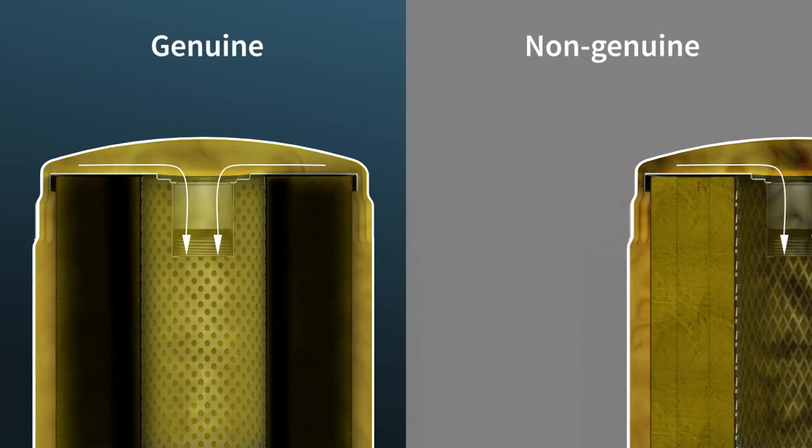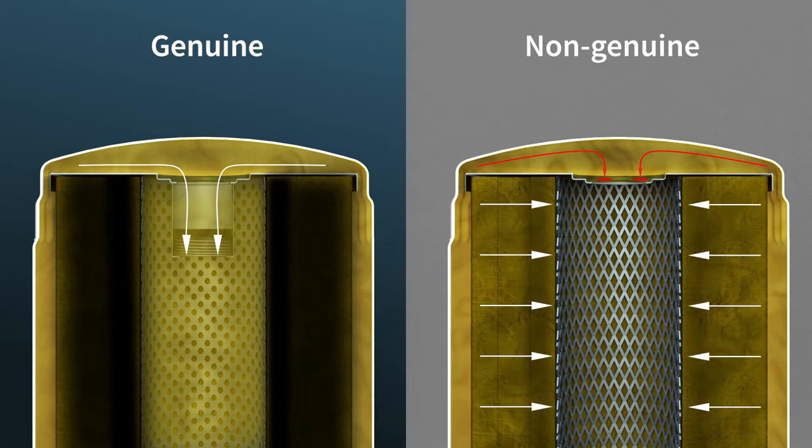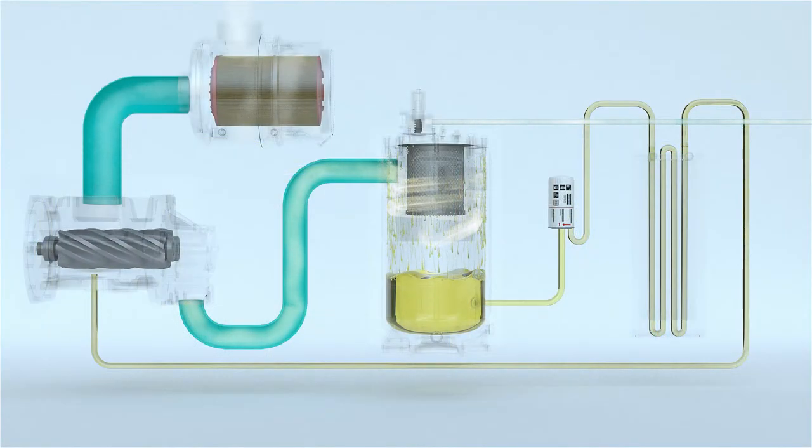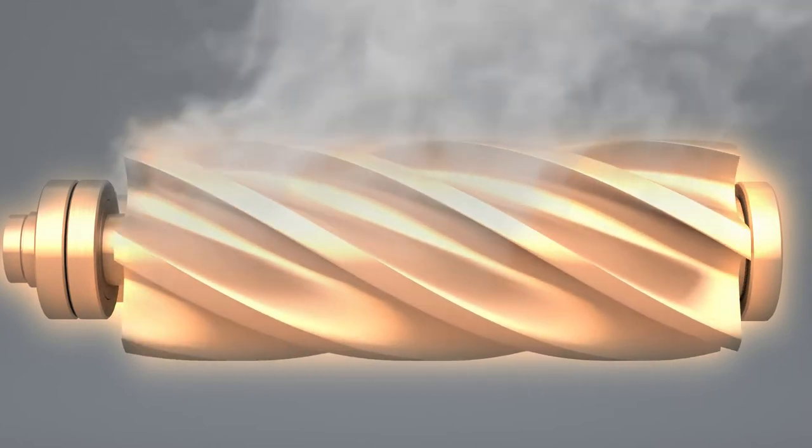In the absence of a bypass valve, a clogged filter can lead to a catastrophic breakdown, as no or a limited amount of oil is sent into the oil circuit, causing bad to no lubrication and leading to metal-to-metal contact, increased temperatures, and so on.